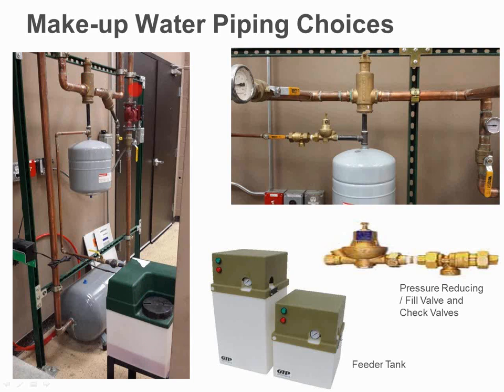If you look at the picture to the right, this basically is the same setup, but instead of having a feed tank here, we have basically a pressure reducing valve and a backflow preventer. If you start where the ball valve is and go to the right, the first thing there is a dual check backflow preventer. Okay, this is required by most codes. Some of the codes in the village have even gone to the point of requiring an RPZ valve on residential systems. So at that point, you have to bring in a qualified plumber and everything else to make sure that valve is certified every couple of years.